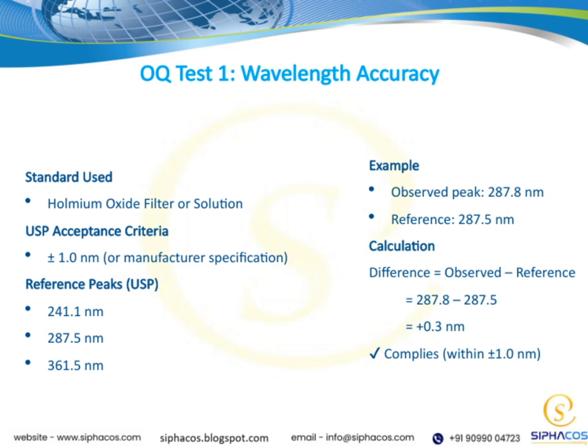Since this difference is within the acceptable range of plus or minus 1 nanometers, we can say it complies with the standards. This is part of our OQ Test 1, which focuses on wavelength accuracy. The standard used for this test is a holmium oxide filter or solution.